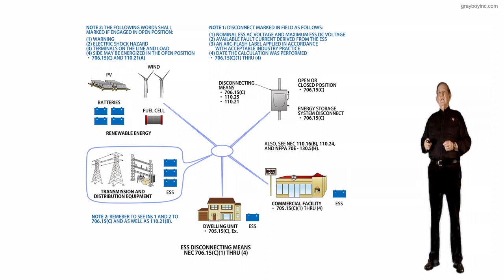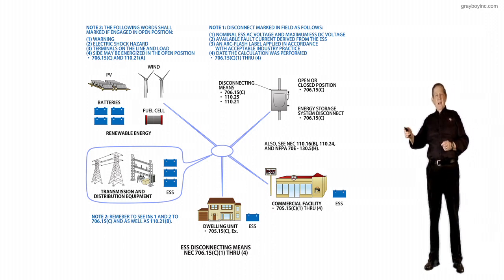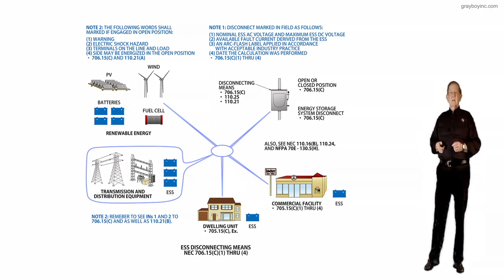Bullet three: field marked and not handwritten. You just can't be field marked with handwritten information. That's the basic rule, 706.15A2.